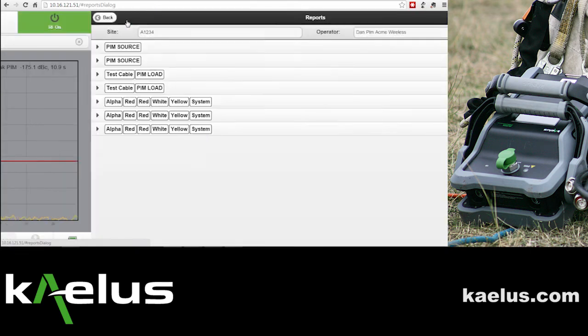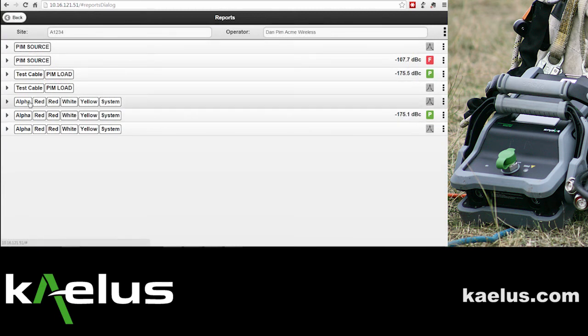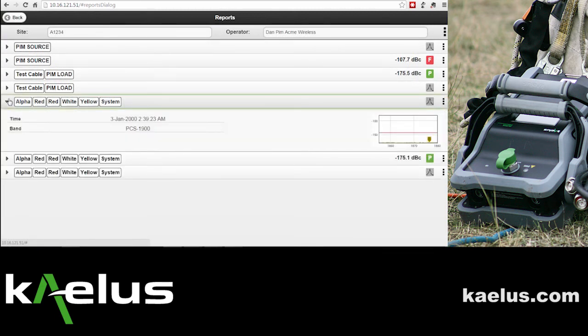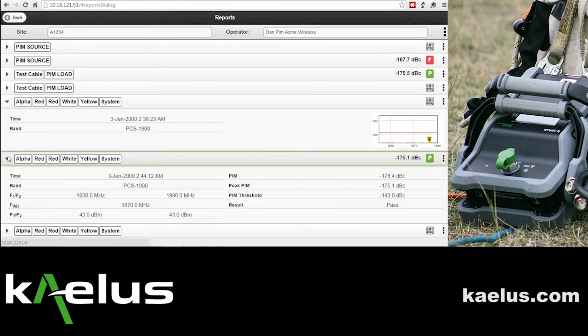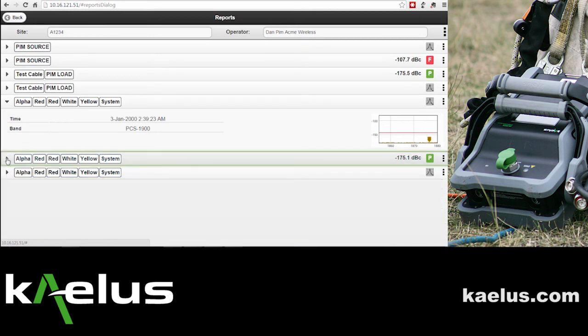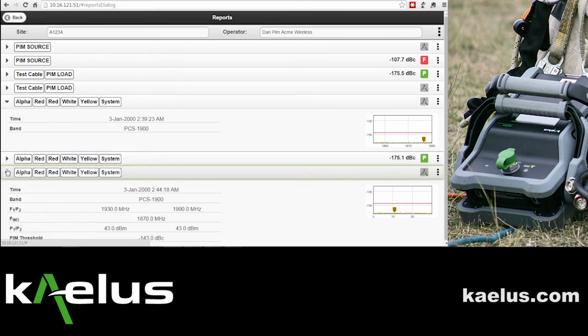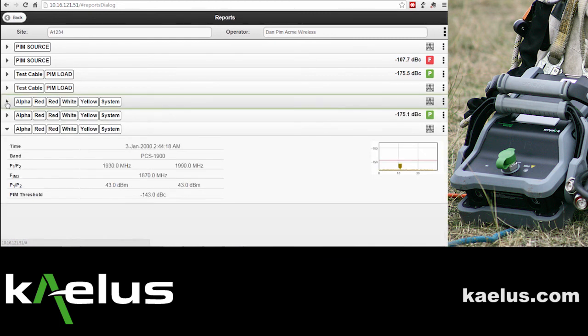Again, in checking in the report, we'll see that we've done the system frequency response using the spectrum monitor for this RF path. We've done a pass-fail, and finally we've added a time trace to indicate that the dynamic testing was done and what the results were for each connection in that system.